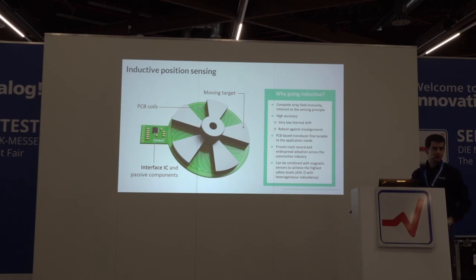It's also a very accurate technology because everything is determined in the end by the geometry of the coils and of the target, and their relative position, and these change very little over temperature. We're not relying on the properties of a semiconductor that change strongly over temperature or stress, and that's key to having very stable and very good accuracy. The sensor itself can also be made very immune to mechanical misalignments if done well.